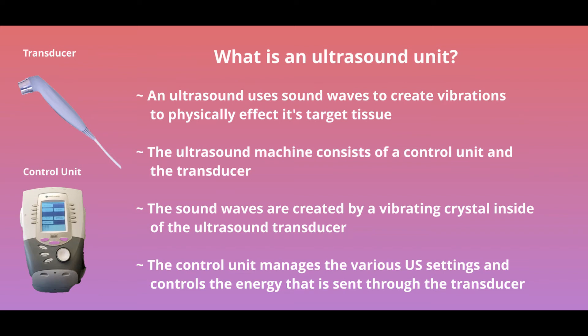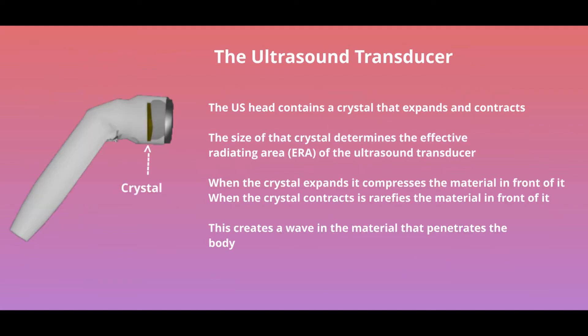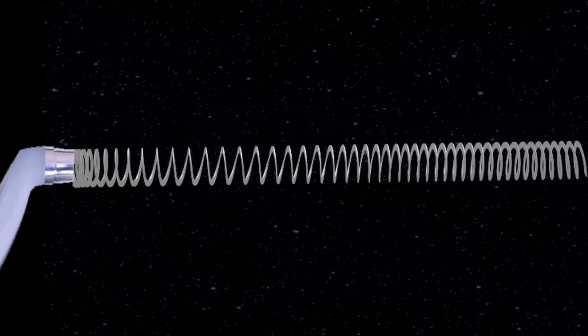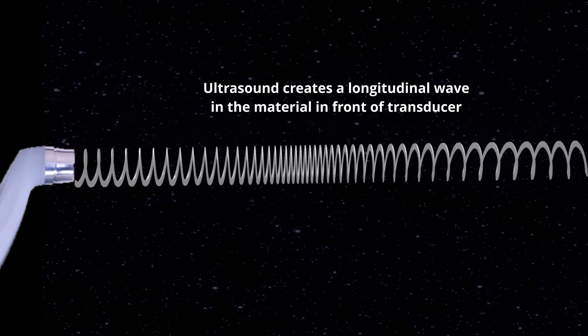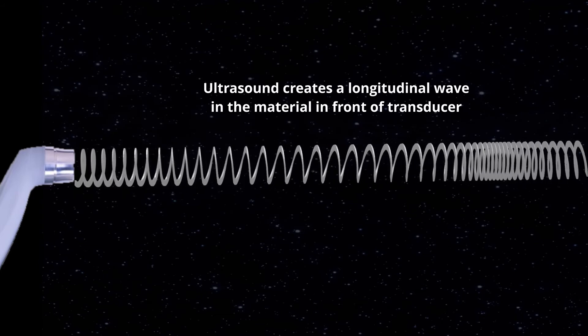The ultrasound unit consists of a control unit and a transducer. The control unit determines the amount of energy that's sent to the transducer. The transducer converts electrical energy into sound waves. The sound wave is created by a vibrating crystal inside the transducer. It's the crystal inside the transducer head that determines the effective area producing energy. We refer to this area as the effective radiating area or ERA of the crystal. The expansion and contraction of the crystal creates a longitudinal wave that travels out from the transducer head.